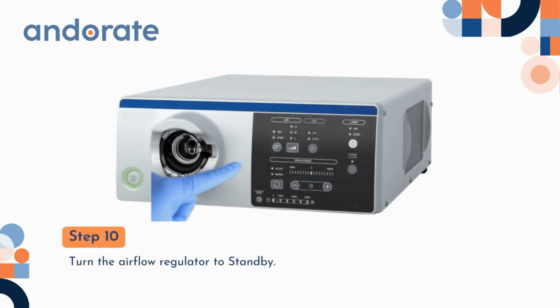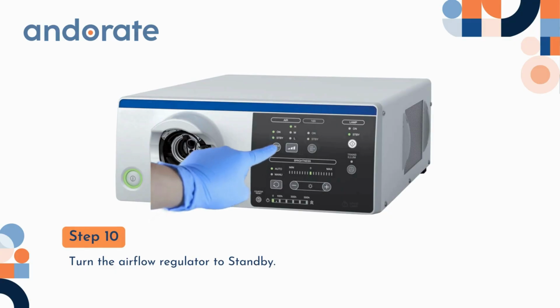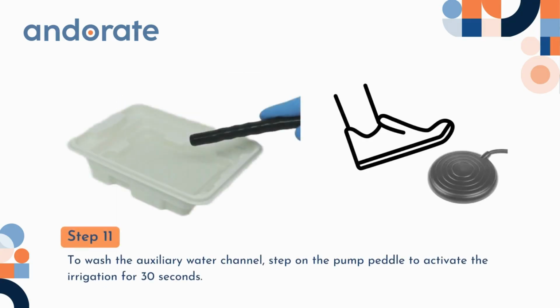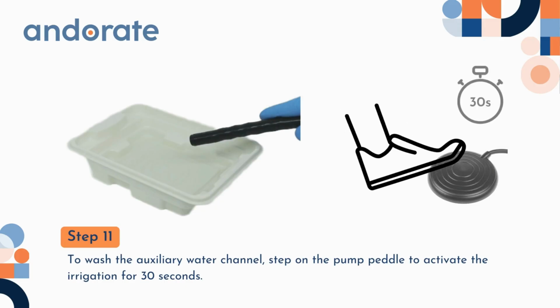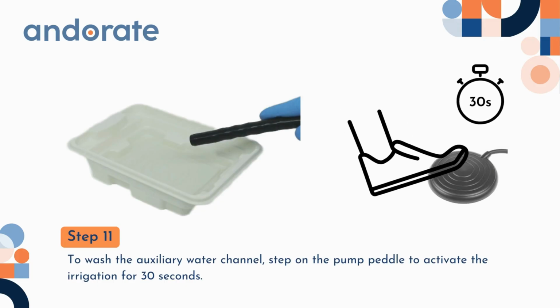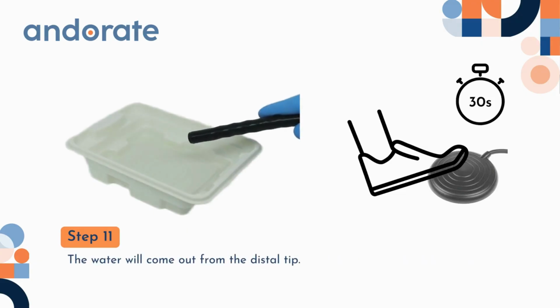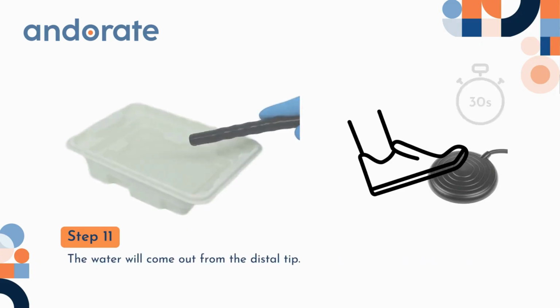Step 10. Turn the airflow regulator to standby. Step 11. To wash the auxiliary water channel, step on the pump pedal to activate the irrigation for 30 seconds. The water will come out from the distal tip.